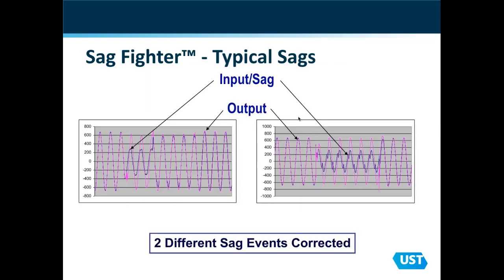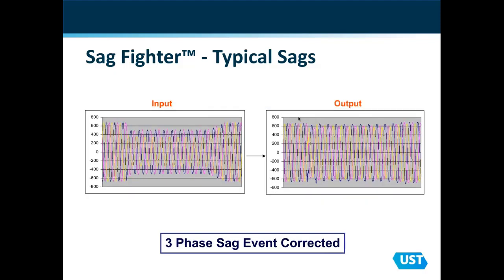This is just a simple representation, scope shot, if you will, of a sag event occurring with the blue sine wave, and then the pink sine wave showing the correction and how it immediately gets back to a full sine wave and a complete correction. Same type of scope shot, only here we have a 3-phase event. So you can see that on the input on the left-hand side of your screen, and then how quickly the Sag Fighter will make the correction and give you nice clean output.